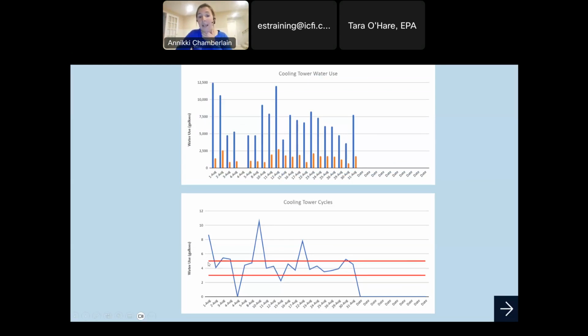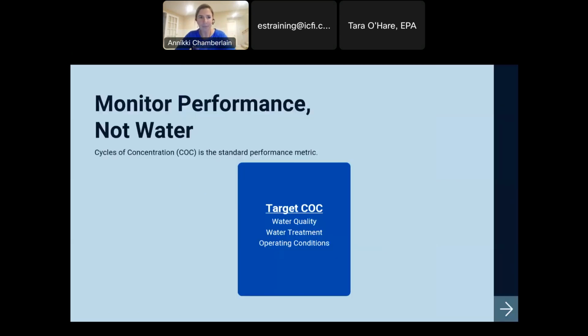So now we say, okay, really my cycle's goal is 4. Anything above 4, like above 5, I probably have a mechanical failure, like maybe a stuck open or a stuck closed blowdown, maybe some overflow, or anything below 3, again, maybe a mechanical problem, like maybe my blowdown valve is stuck open. It's going to drop that efficiency. So we have gone from basically no information to now I can basically tell the efficiency of my cooling tower every day, all part of normal routines, just cost 1 additional meter.